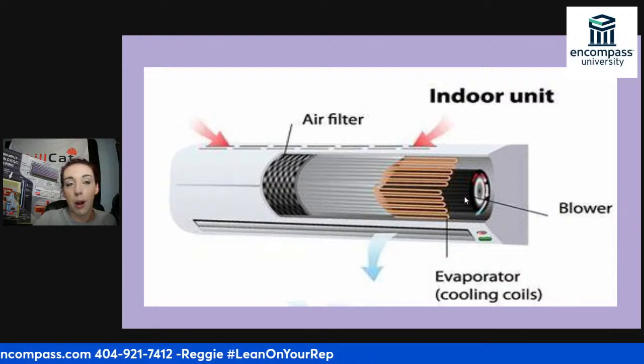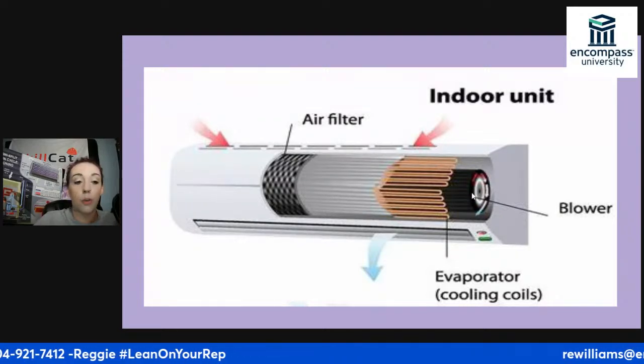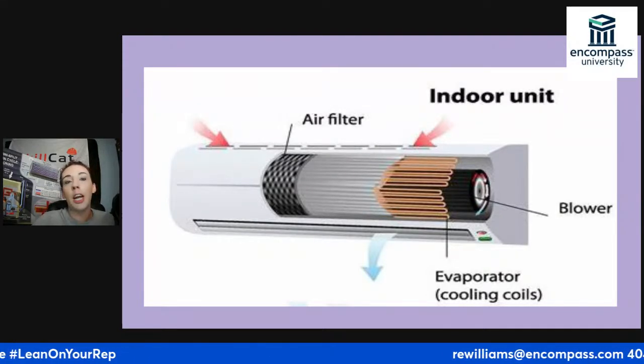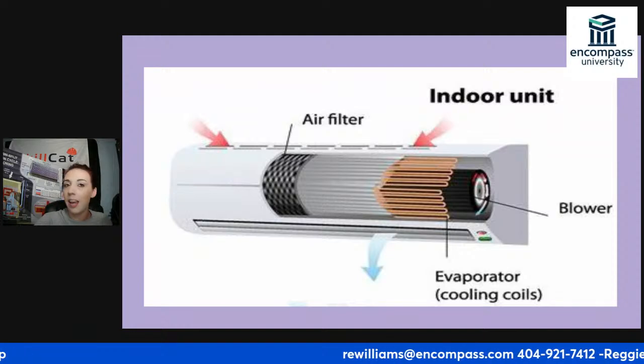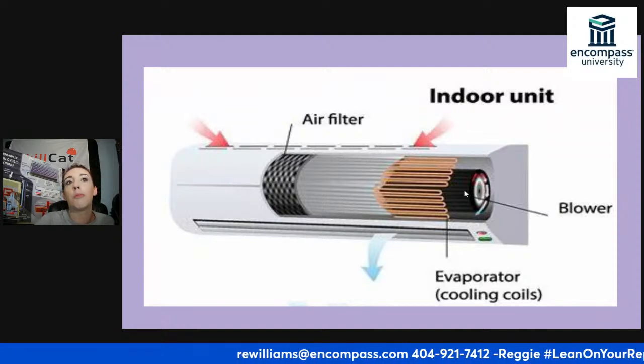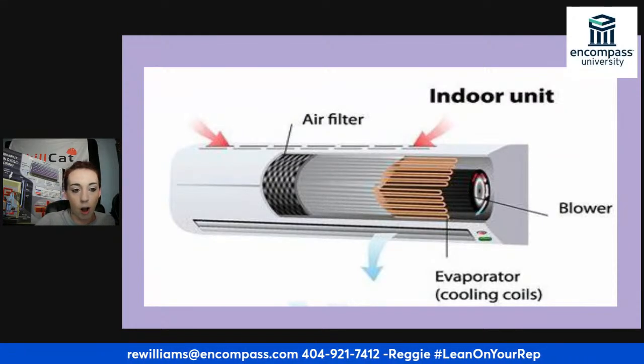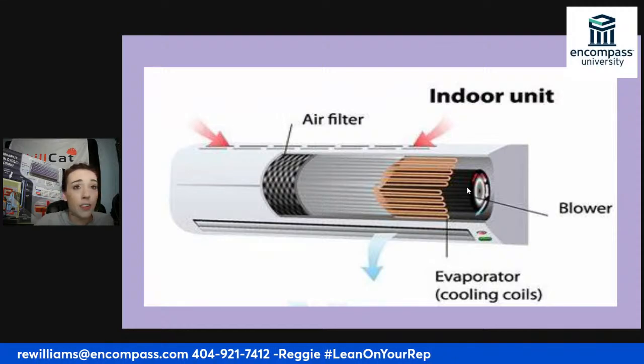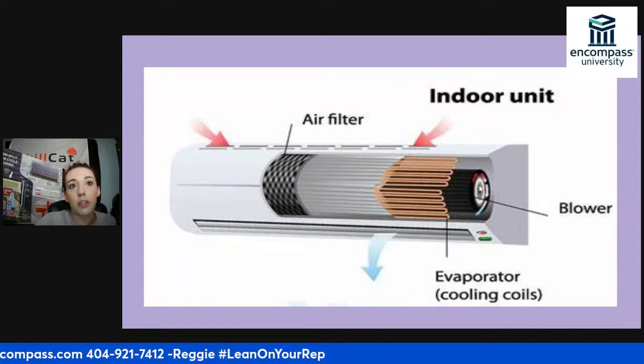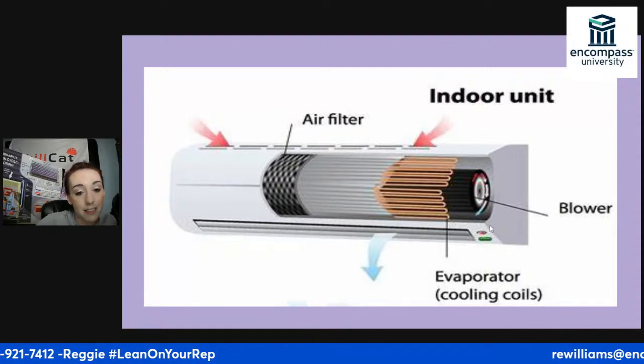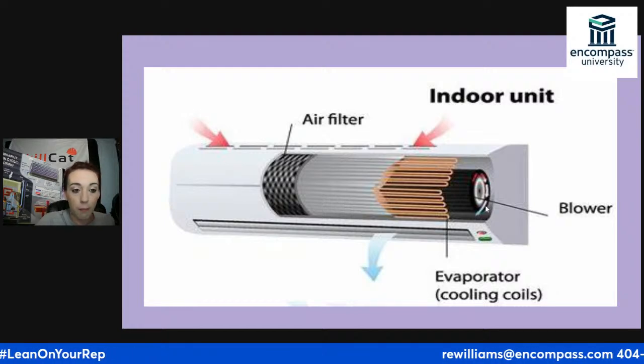And there are certain products you need to use in order to clean that. But make sure in any application whatsoever, you need to check this blower wheel on every maintenance call. If it seems gunked up, even if it just seems like dust, this blower wheel can be pulled. It's not an easy job, but it's a necessary job. So we don't like to pull the blower unless we have to.